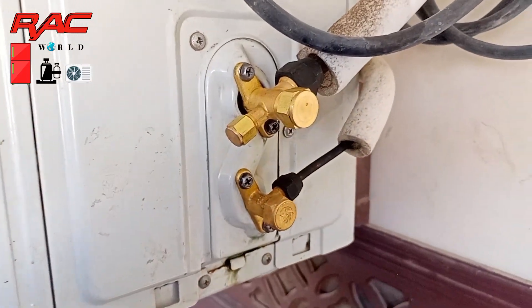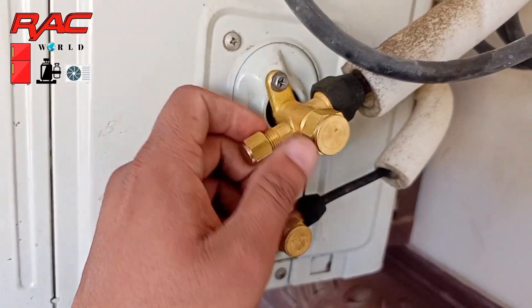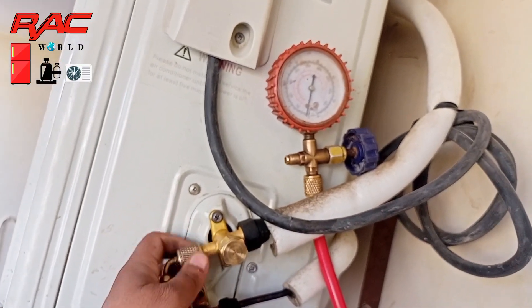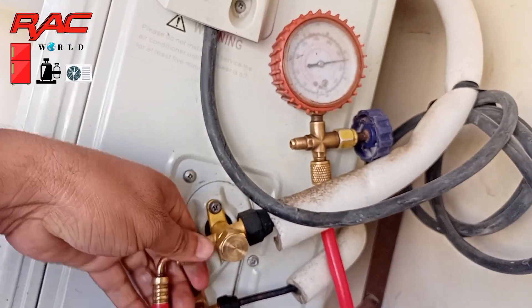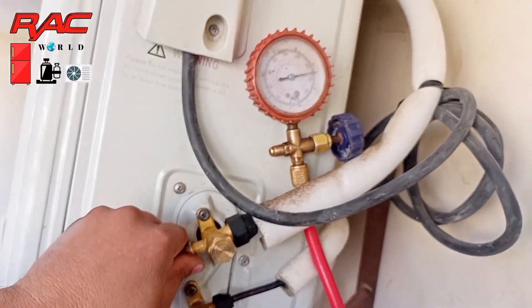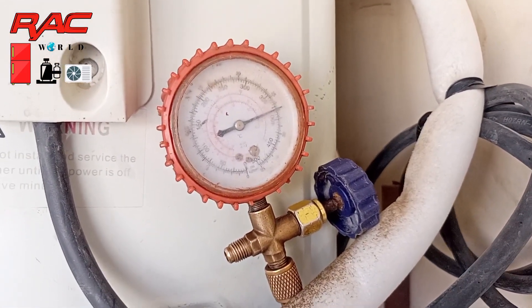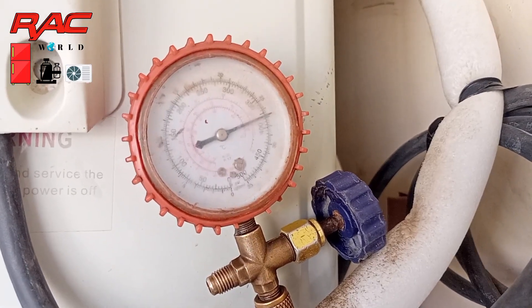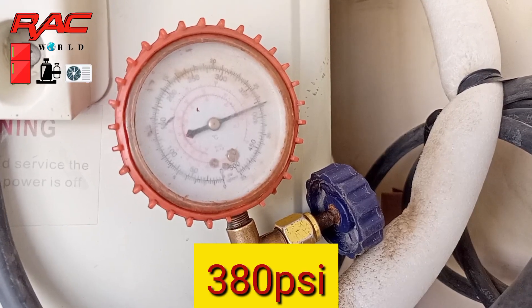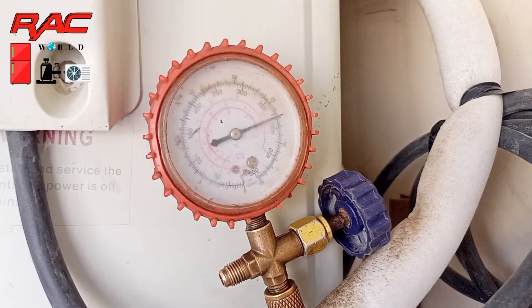First of all I will remove its dust cap. For this purpose I need a high pressure manifold gauge. I have connected my high pressure manifold gauge with its charging valve, and you can see on your screen it is showing 380 PSI running pressure.